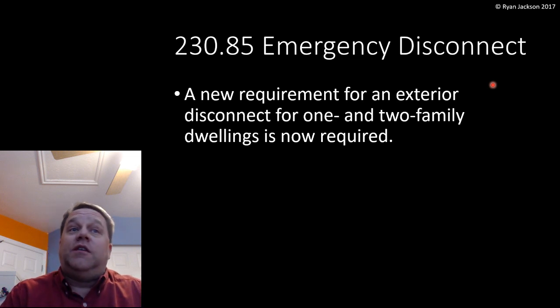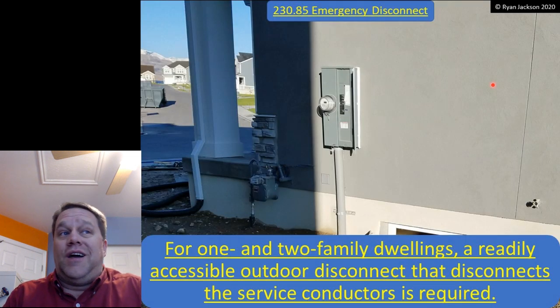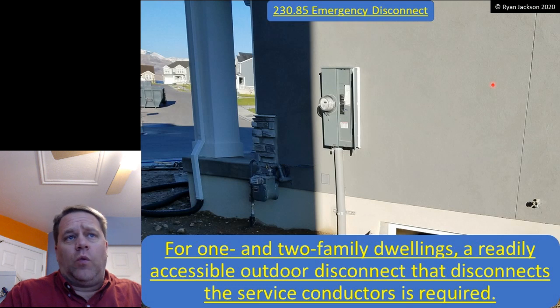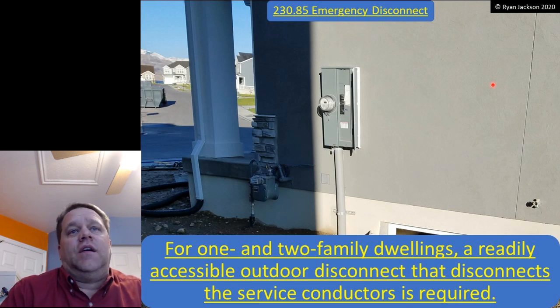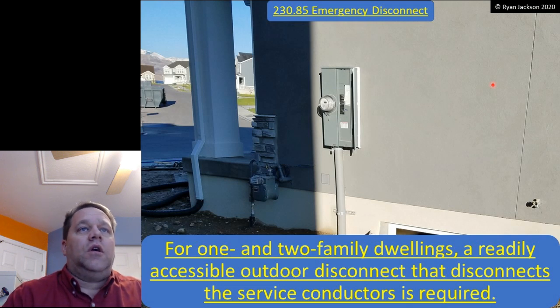Well, that's not something you're going to see anymore. Now your area is going to look a lot more like my area. So for one and two family dwellings, a readily accessible outdoor disconnect that disconnects the service conductors is now required. Okay, so you need to walk up to this house and be able to shut it off from the outside.